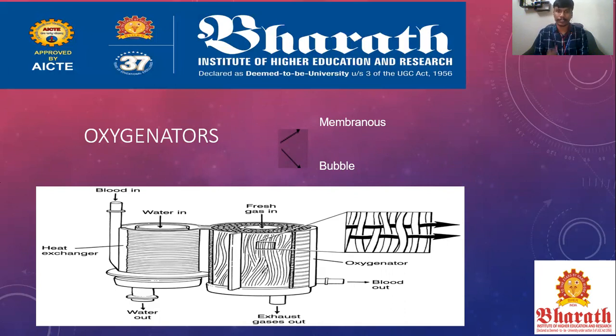And here we are using two types of oxygenators. One is the membranous oxygenator, another one is the bubble oxygenator. The oxygenator which adds the O2 molecule through a membrane to the blood is known as a membranous oxygenator. The oxygenator which adds the O2 molecule to the blood by bubble particles is known as a bubble oxygenator.